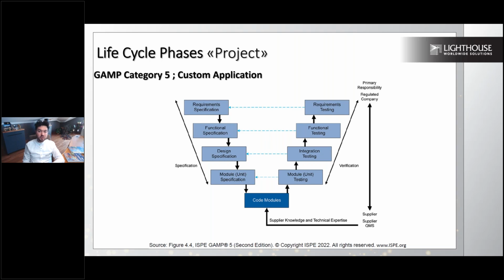This is described as operational qualification. Requirement testing, which is the overall performance qualification of the system, addresses your user requirement specification.